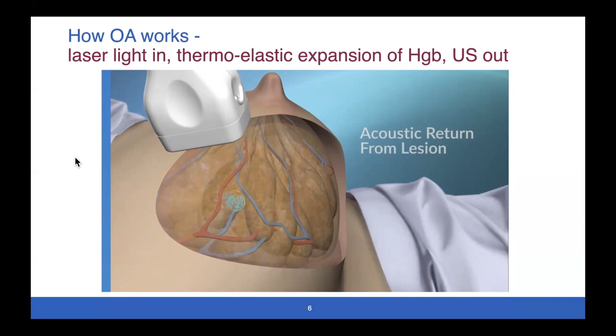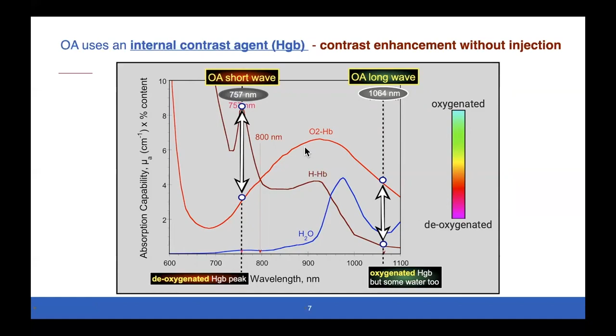Now we use these two different wavelengths, and you don't need to remember the numbers. Just remember that the short wave I've colored red because we code deoxygenated blood as red, and the long wave I've color coded as green because that's absorbed primarily in oxygenated blood. And we've chosen these wavelengths to get the maximum distance between oxygenated and deoxygenated, where there's the most difference, and also to avoid the confounding water peak. So our color display shows that red and fuchsia is deoxygenated, and green and aqua is oxygenated. And it was meant to be like a stoplight. Red means, hey, look at me, I'm dangerous, stop at the intersection, don't run through the intersection. And green means it's okay, we can go. Now, obviously, that's an oversimplification.